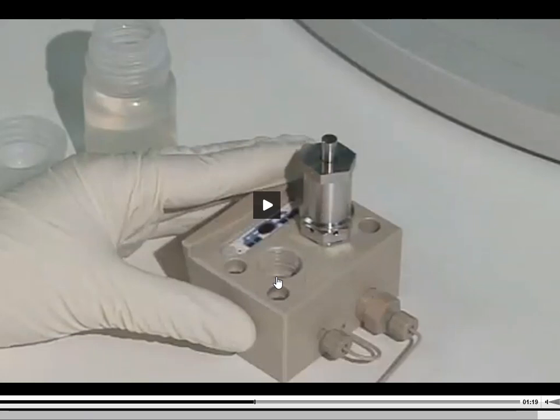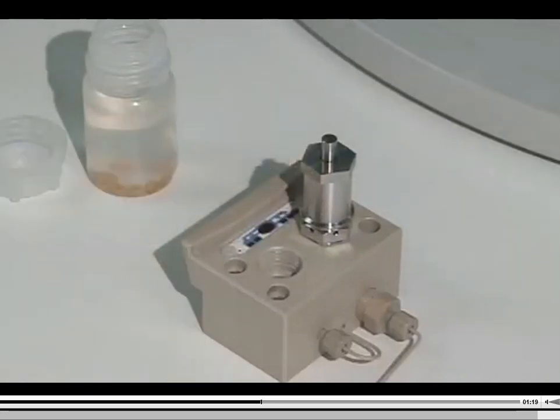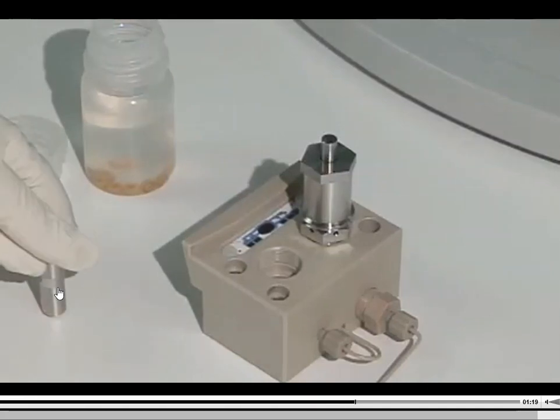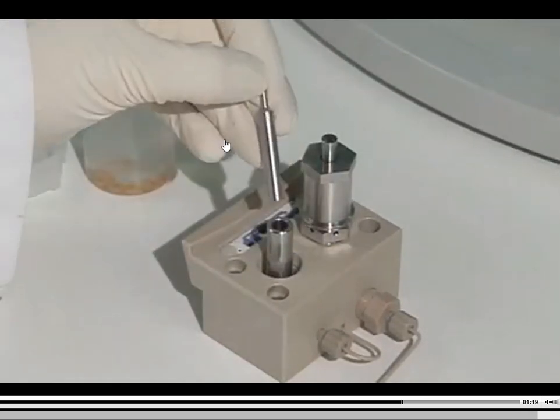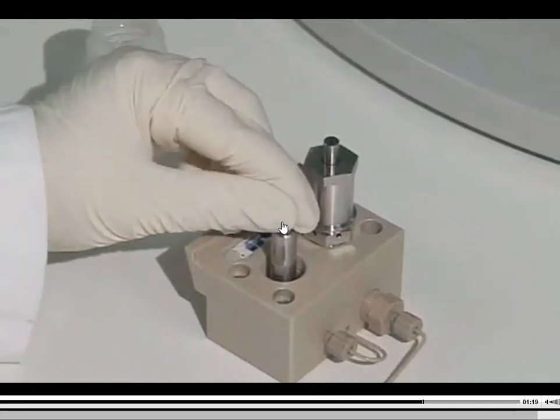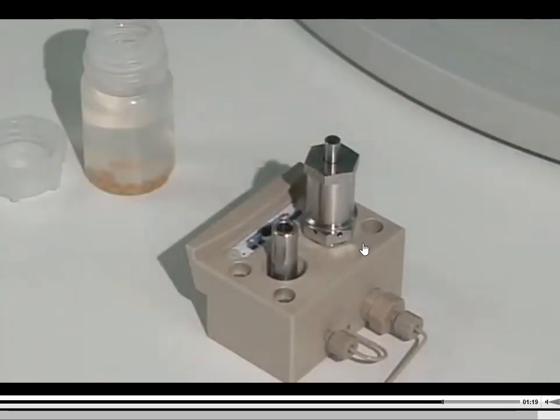If these seals go bad, what's going to happen is your pump begins to leak. If you have a leaky pump, then your flow rates are not going to stay the same. Your pressure cannot build up. You're going to have leaks all over on the inside of the instrument. Good luck if the instrument runs for you at that time - you're probably not going to be able to do anything with it at all. So now this person is going to have this kind of a jar back here in the back. These seals are probably stored in some kind of alcohol just to keep them clean. There they are. Now there's an extra little tool in the kit that you just pop that seal back onto the bottom, and that gets guided back into the pump. And that same tool that you use to screw that thing out of there, well that basically pops that new seal back into place. And that's all that you've got to do.